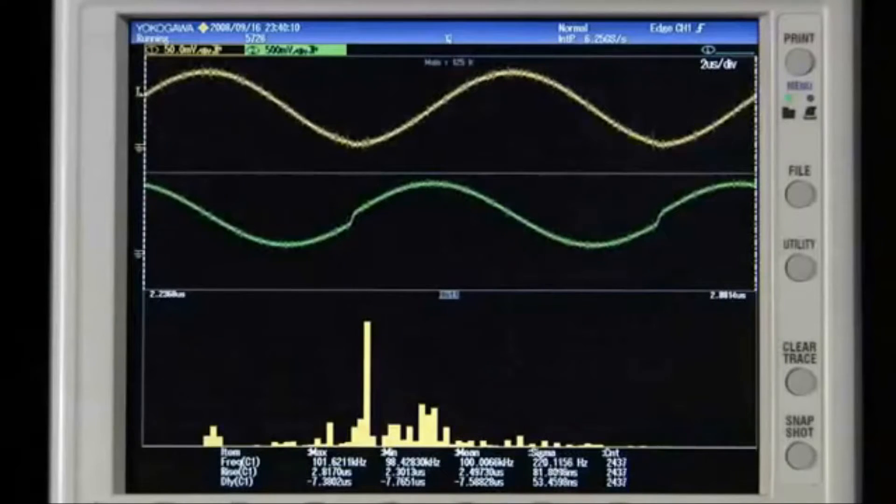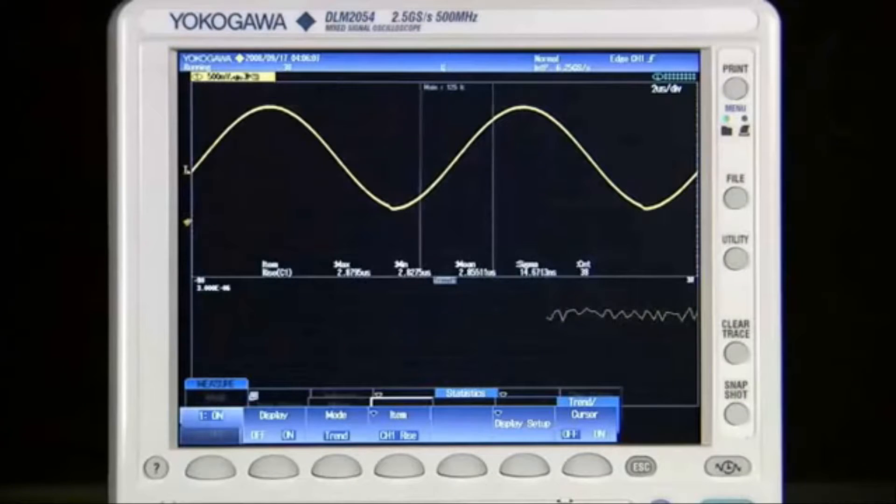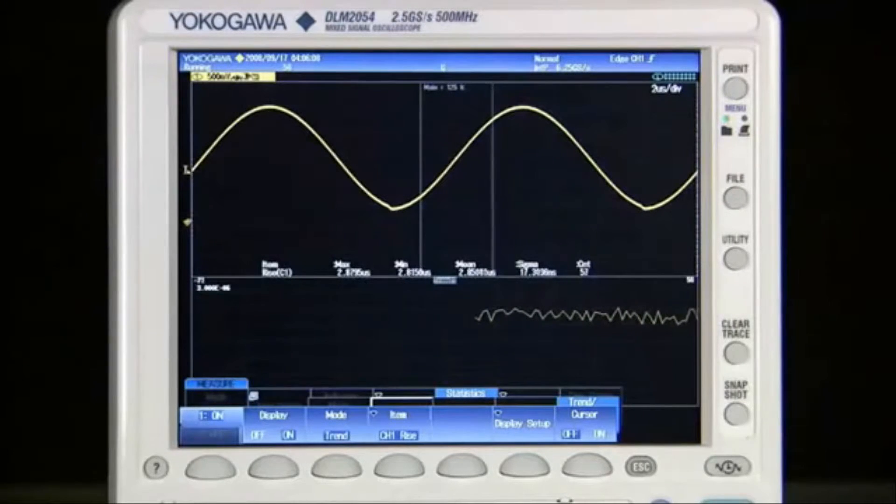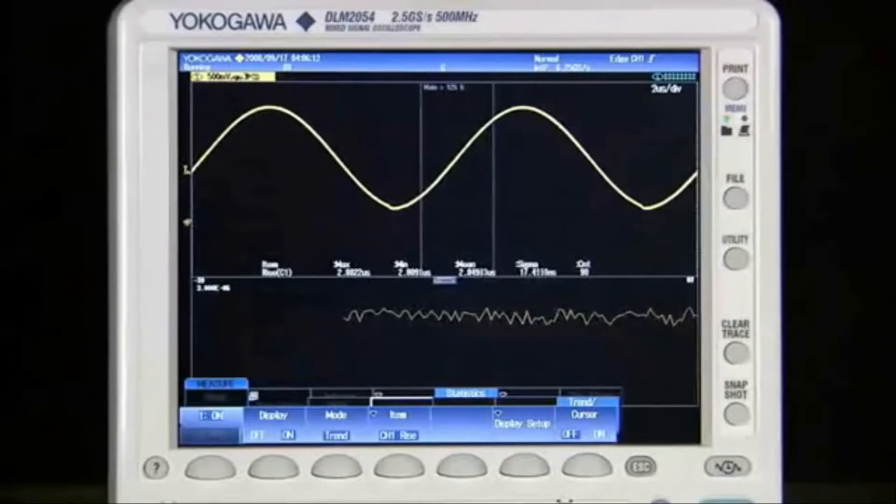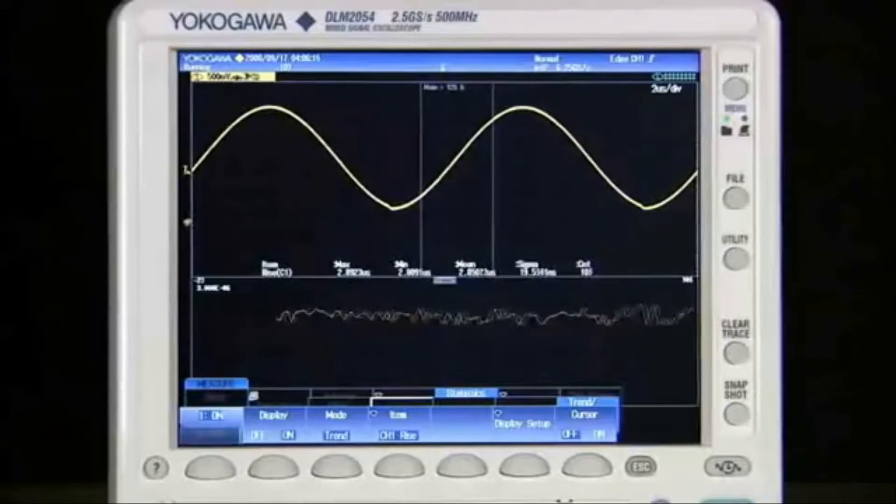The DLM2000's analysis engine can also create trends and histograms. For example, you can monitor rise time trended over several minutes. This gives you insight into stability or long-term behavior of your signals with changes in temperature or other system components.